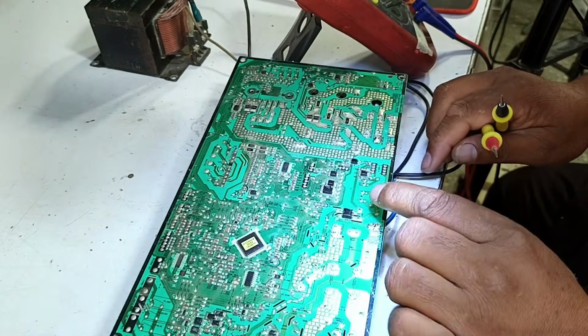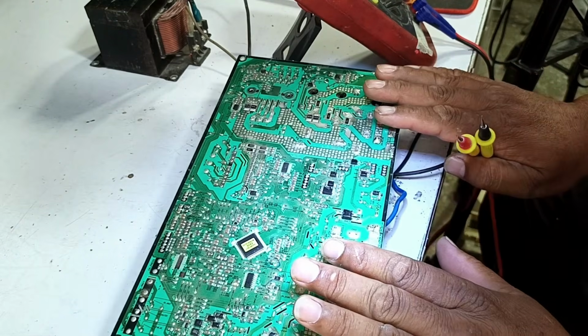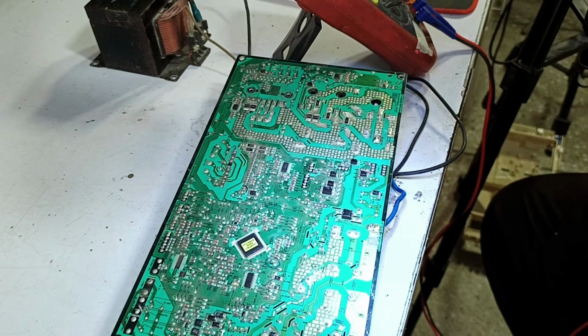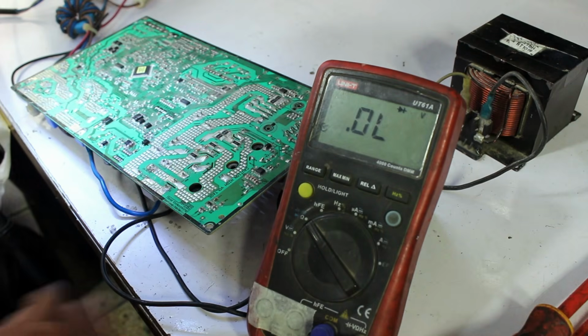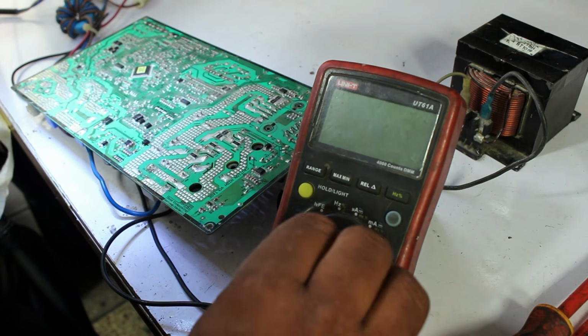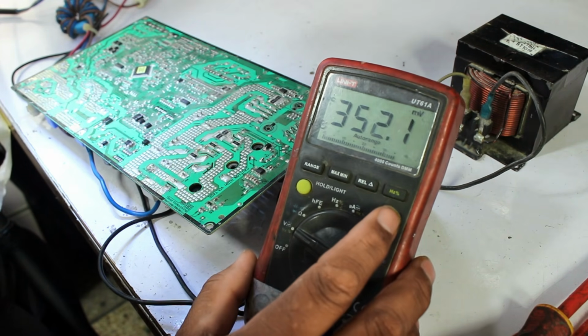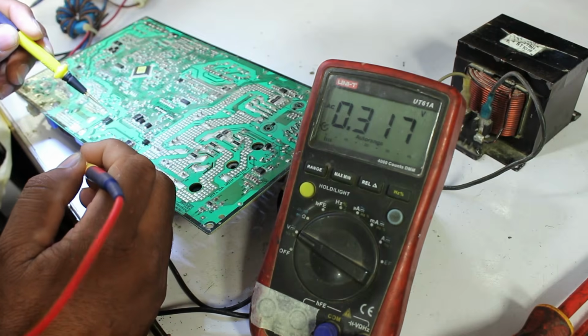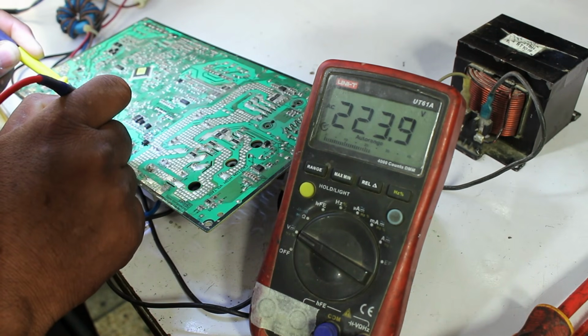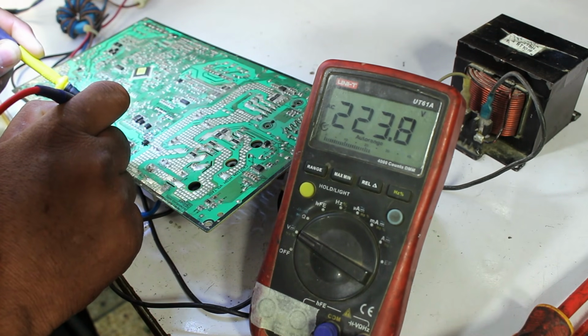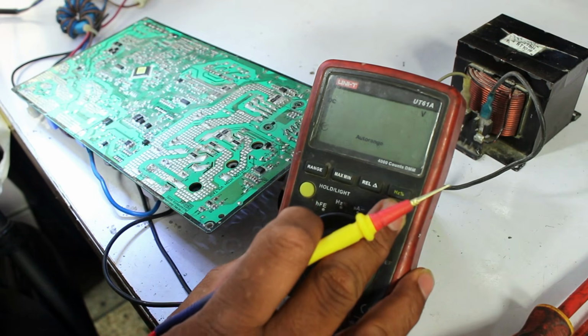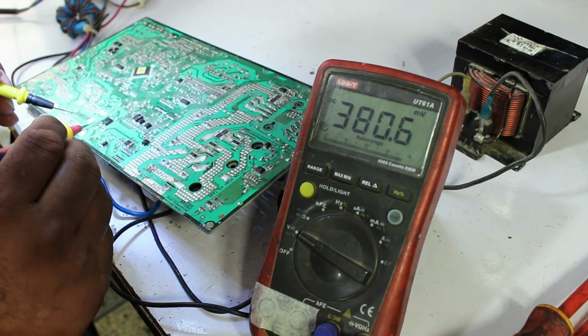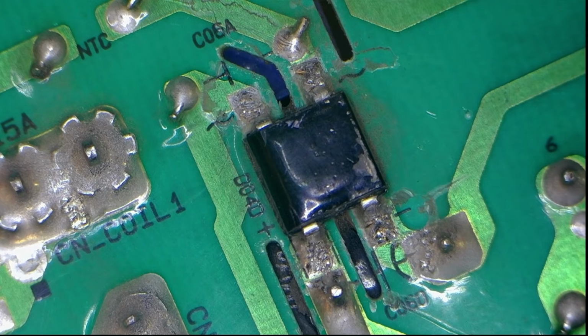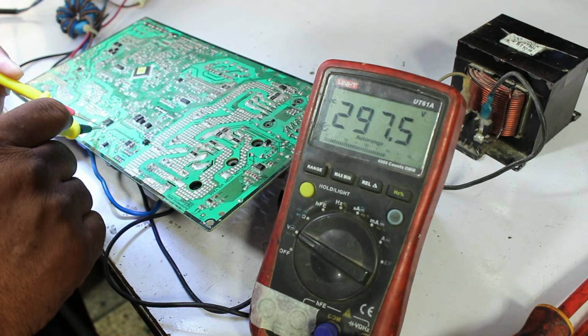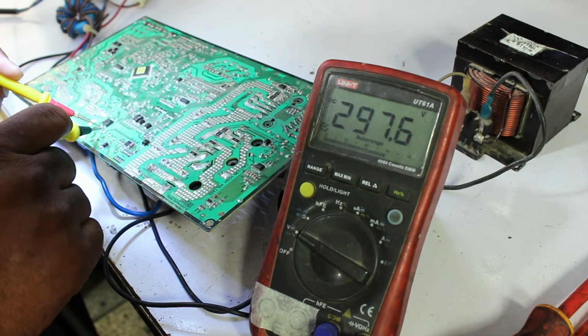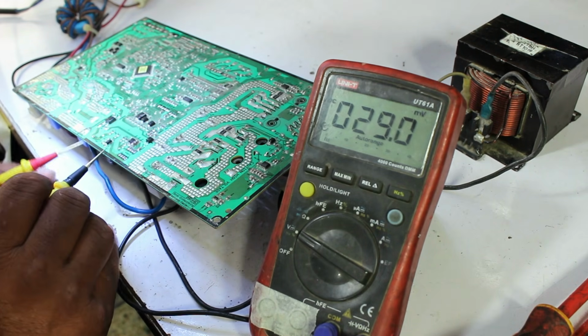Since there is no short circuit in this PCB, we can directly apply electricity and check it. So I connected the power and electricity has reached here. I will set the multimeter to AC mode to check it. On the AC side of the bridge rectifier, 224 volts are properly reaching, which is completely fine. Now I will switch the multimeter to DC mode and check the DC side, negative and positive. As you can see, 297 volts are being generated on the bridge rectifier at this time, which means electricity is properly entering here.